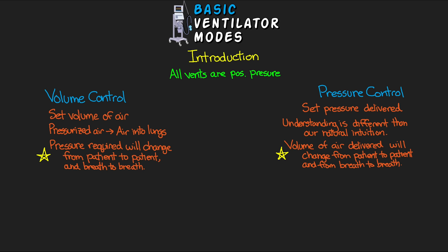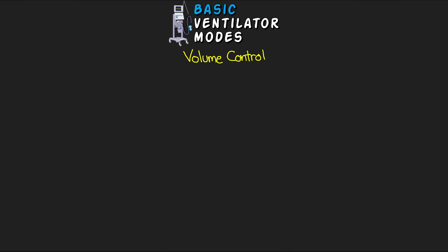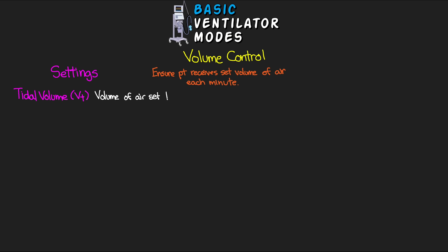For this lesson we're sticking to volume control. The main principle is that we want to ensure our patients are receiving a set volume of breath each minute. Within this category there are different modes that play different roles in impacting our patient's work of breathing. To understand the differences between these modes, we need to talk about some of the settings. The first setting is tidal volume, abbreviated Vt — this is the volume of air set to be delivered with each breath.